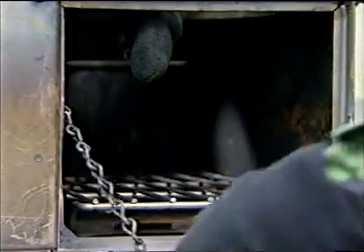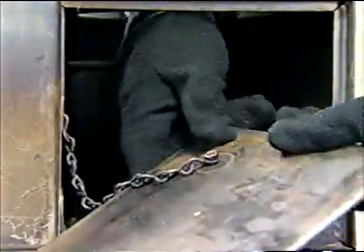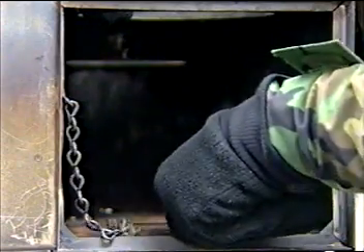To install the burner cover assembly for solid fuel operation, slide the front door latch to the left and open the front door. If the burner cover assembly is currently installed in the door frame, remove it and allow it to hang from its retaining chain. If the solid fuel grate is installed, remove the grate and install the burner cover assembly smooth side down over the burner assembly opening. Slide the cover back toward the rear of the heater until its back edge engages in the burner cover retaining clip.